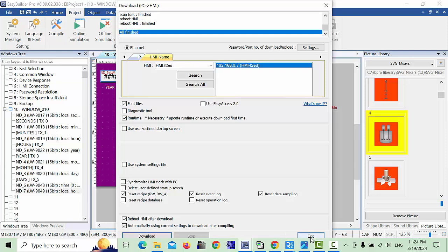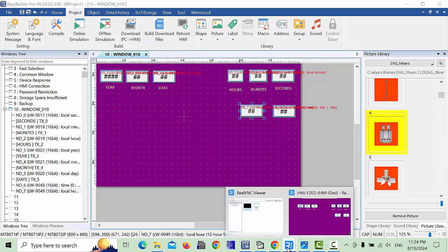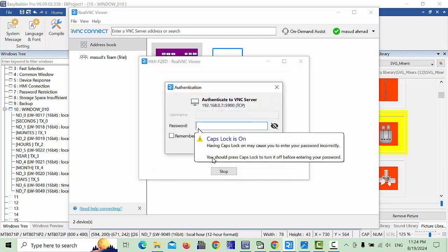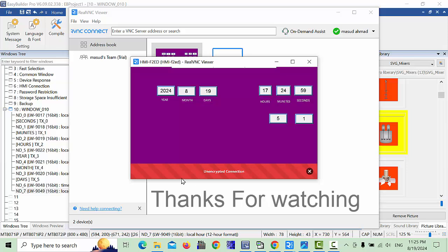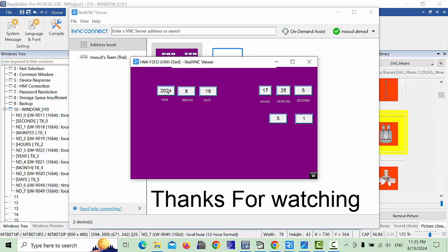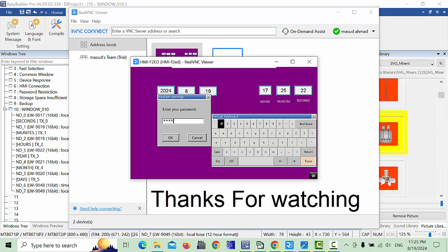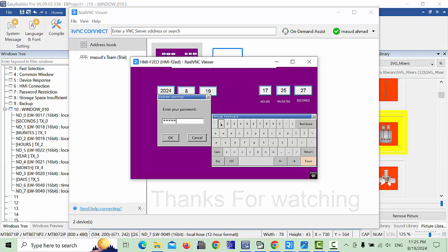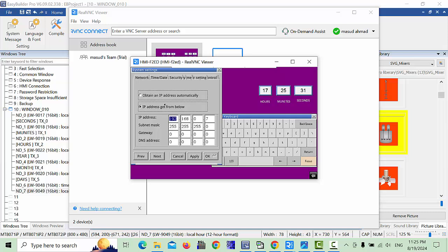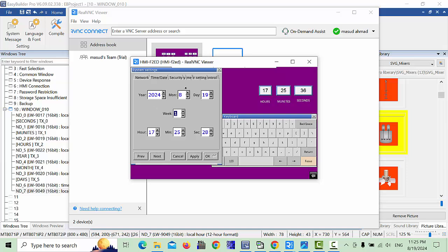There is another way to change the time from the HMI. Click Exit, go to your HMI screen, and since we removed input access, you can no longer change it directly. Instead, go to Settings and enter the default password — six digits: one, one, one, one, one, one — and click OK. A settings window will open; go to Next and you can see the time and date display.